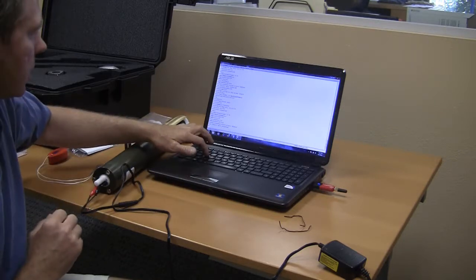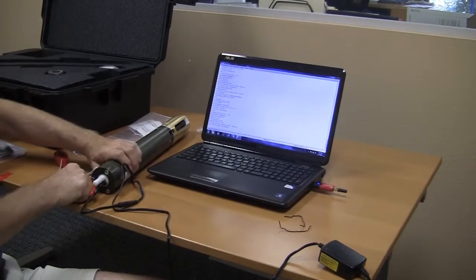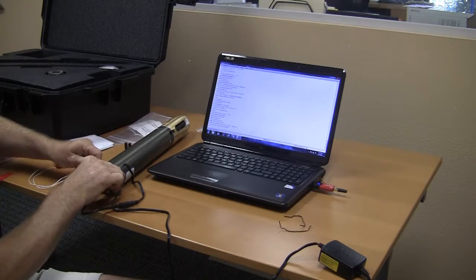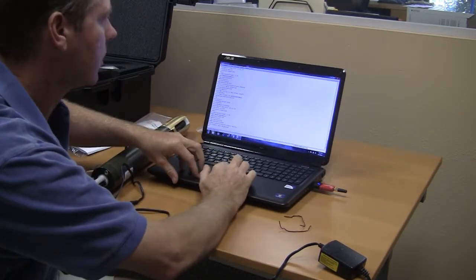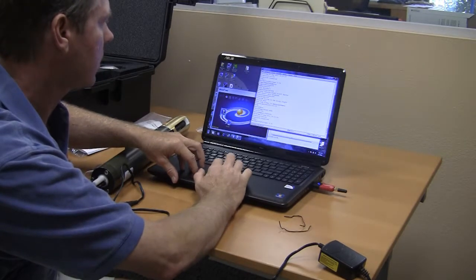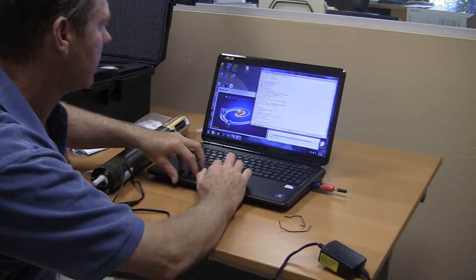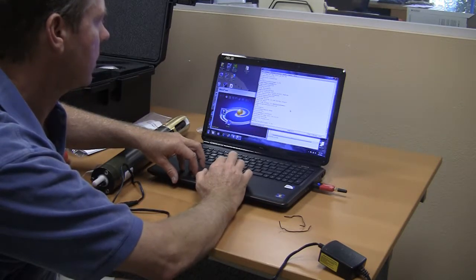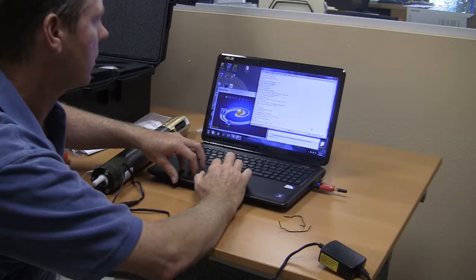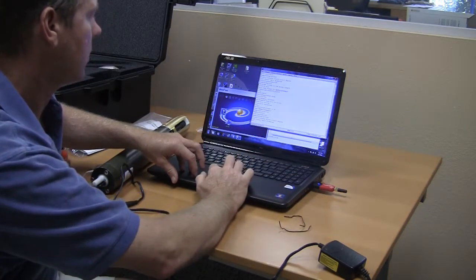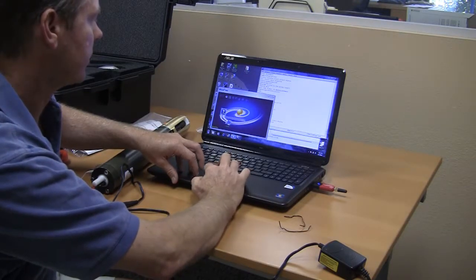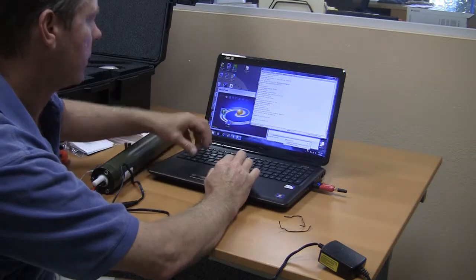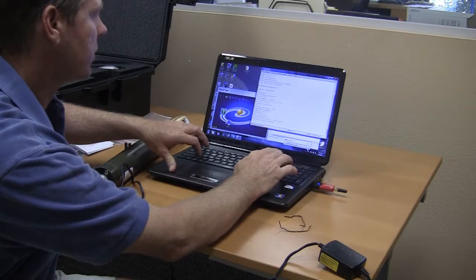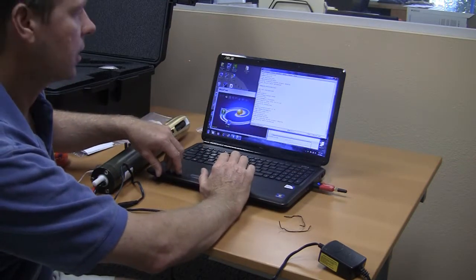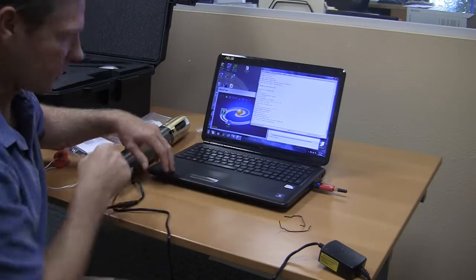So one way to check that, the probe's asleep right now, so we can cycle it again. Press disconnect. Now we're going to connect again. Here as well. Connect to serial port. And there it is. We have connection with the probe again. Now we can check the battery voltage, and it gives you 3.76, just like before. And that's probably an indication that the charging terminals are reversed.